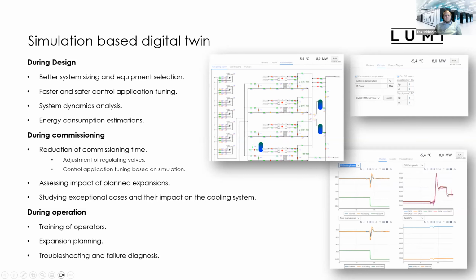We could get the data how the dry coolers will increase the fan speed on the heat load changes, and how it fluctuates, how the outlet fluctuates from the free cooling heat exchangers and from the heat pumps. So this was pretty good, especially during the design phase. Our cooling designers were pretty happy for this tool selection. So during the design, they had better system sizing and equipment selections.